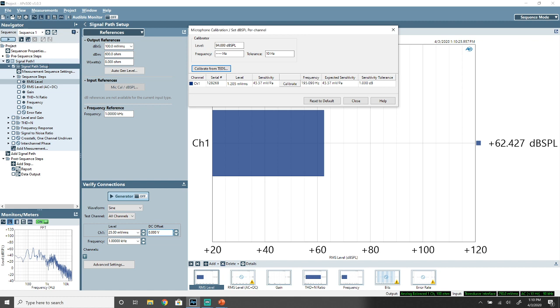But in this case, I have the option to, and I want to be extremely accurate, so I'm going to click TEDs, and I'm going to choose which mic I'm looking at, microphone 1, read from TEDs. What that does is it looks at a small chip that's actually inside the microphone and preamplifier combination that has the actual sensitivity value of the microphone and where it was measured. And that's going to apply that as soon as I say set sensitivity. Okay, I can go ahead and close that with my new sensitivity added. And now I'm ready to go to the next step.